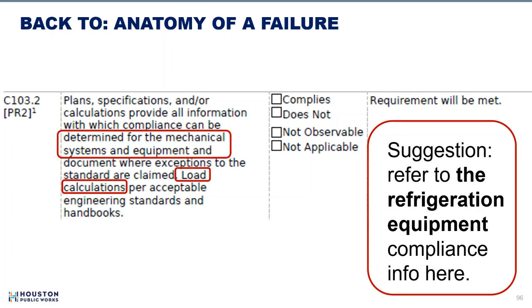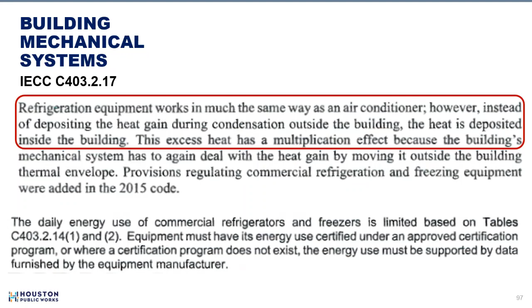Why? Refrigeration equipment works much the same way as an air conditioner, except instead of depositing the heat gain during condensation outside the building, the heat is deposited inside the building. There's usually no flue from a cooler, a freezer, or a refrigerator to the outside. So you are dumping that heat into the building, and then the mechanical system has to deal with that, and the loads are increased, and we need more air conditioning.